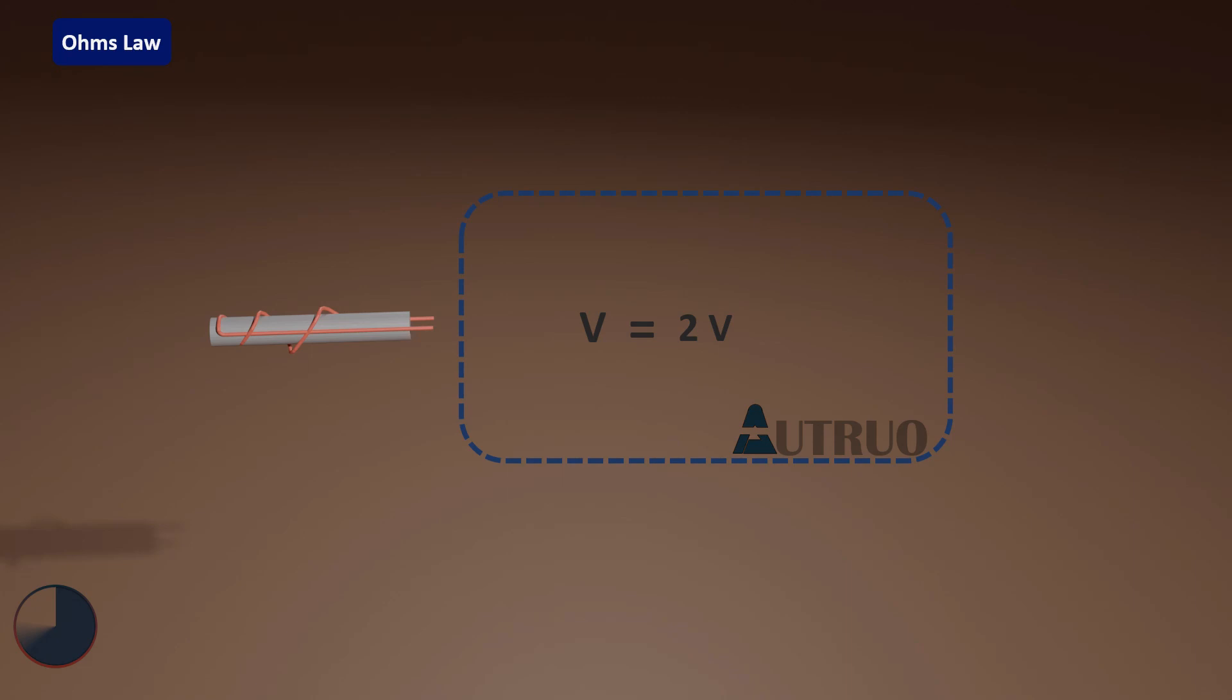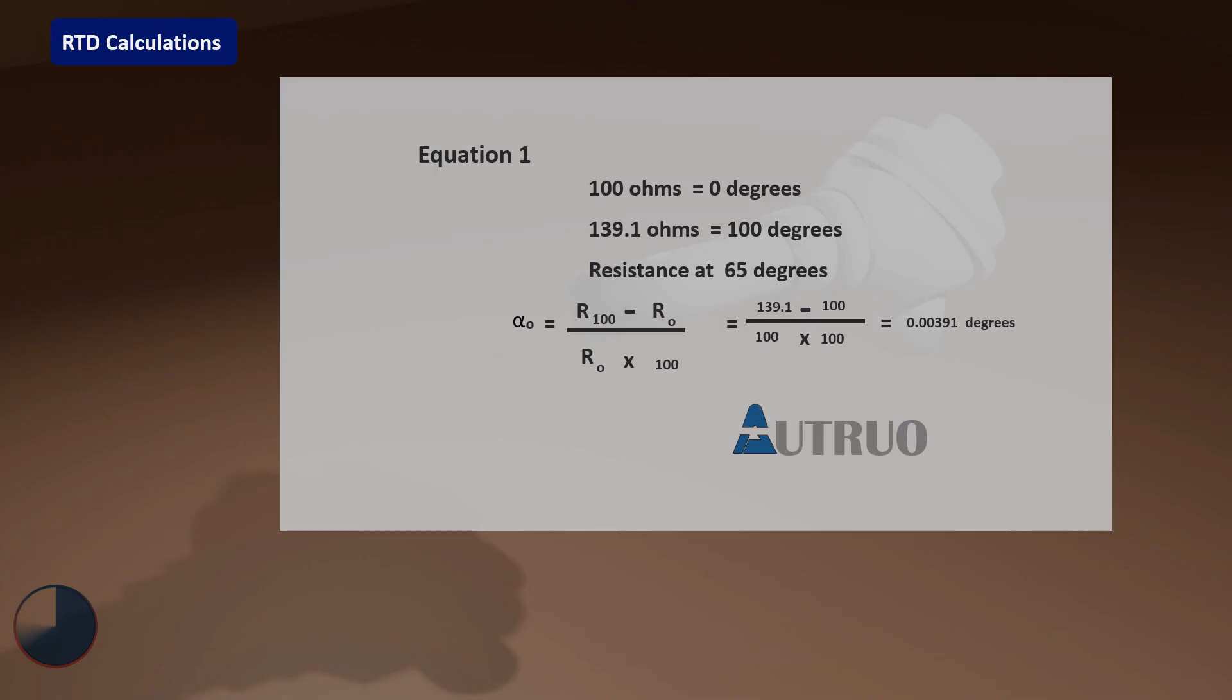Let's also look at this equation. At minimum temperature, the resistance is 100 ohms. At maximum temperature, the resistance is 139 ohms. Now, alpha will equal R_max minus R_min all over R_min times 100. The calculation is: (139 - 100) / (100 × 100) = 0.00391 degrees.